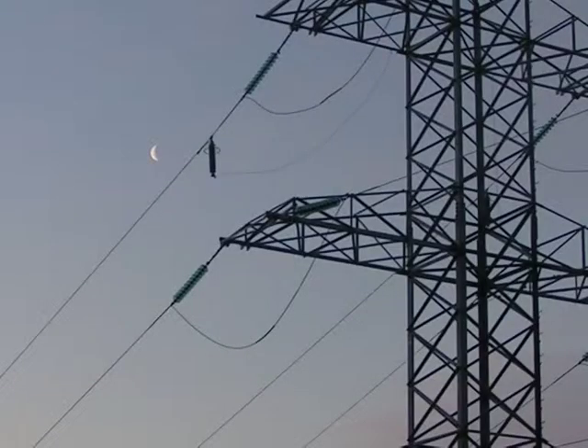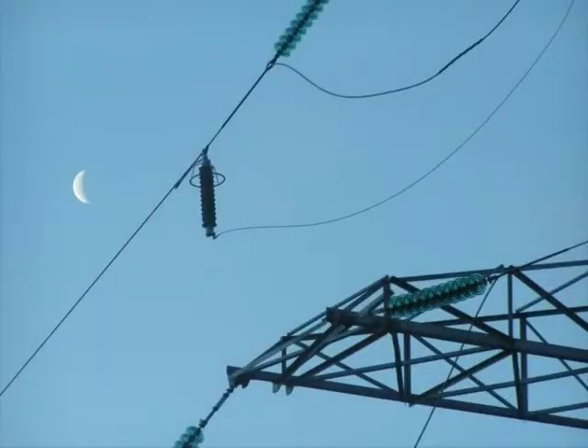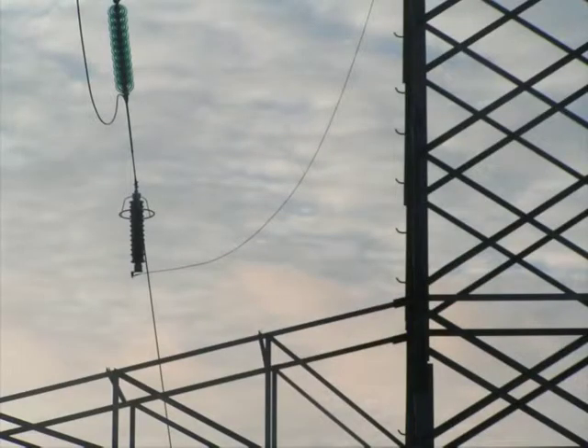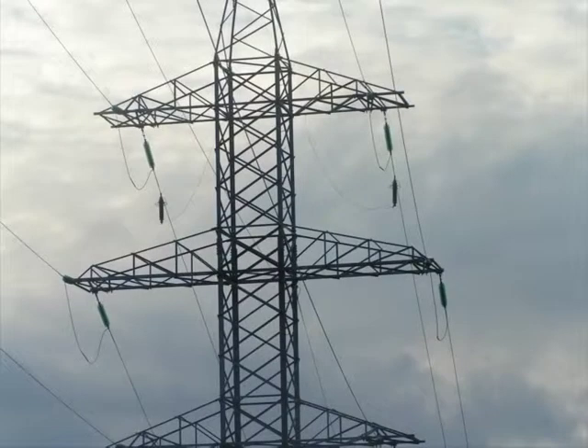In recent years, metal-oxide surge arrestors are installed on towers or overhead line wires to protect the insulation of overhead lines from lightning and switching overvoltages. The need for their use is dictated by the increasing demands on the quality of transmitted energy, reduction in the number of disconnections of overhead lines, and interruption in electricity supply.